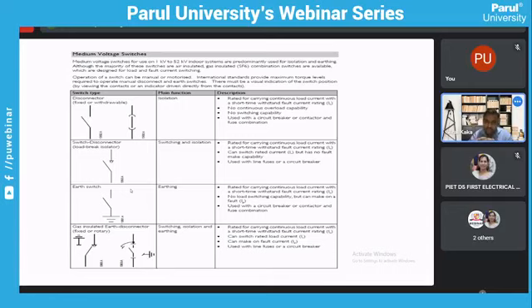an earth. Now this arrangement also changes from secondary GIS switchgear to primary GIS switchgear. The fundamental difference between secondary and primary, from vendor to vendor design, can be seen in that on the secondary GIS switchgears, your 3-position disconnector switch will be towards the cable and your breaker will be connected towards the bus bar. But the arrangement is slightly reversed. Again, this is vendor specific in terms of primary GIS switchgear, and for that the earthing operation is being done through the breaker.